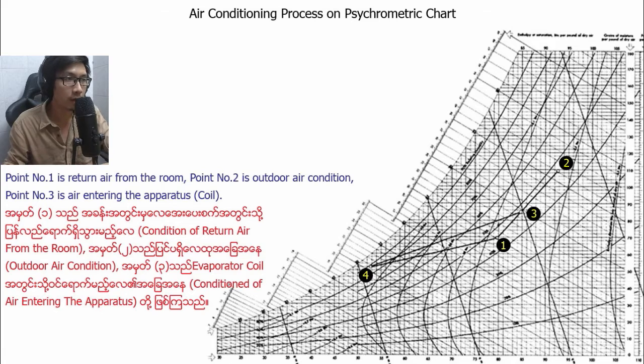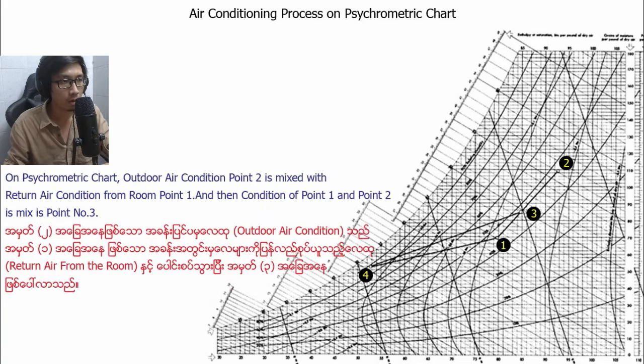Point number one is return air from the room. Point number two is outdoor air condition. Point number three is air entering the apparatus. On the psychrometric chart, outdoor air condition at point two is mixed with return air from the room at point one, and the condition of point one and point two mixed is point number three.